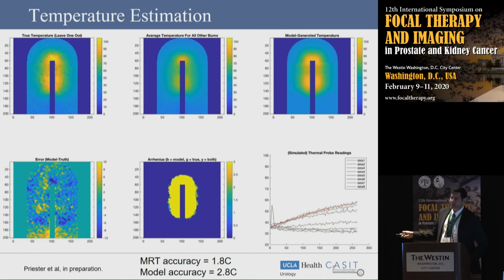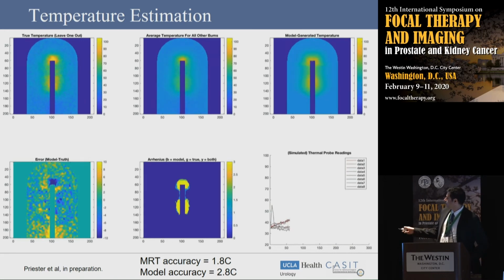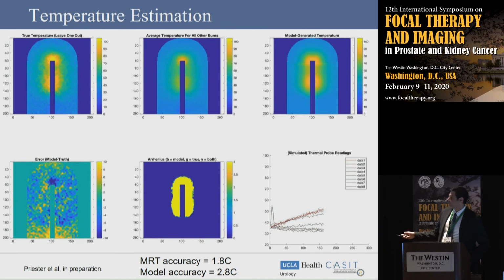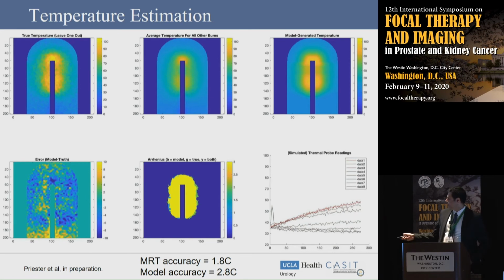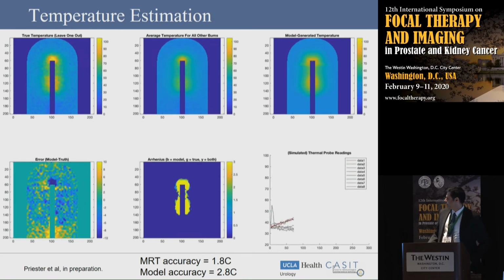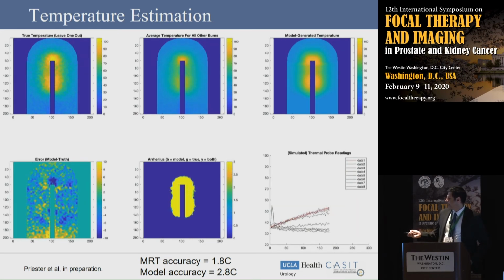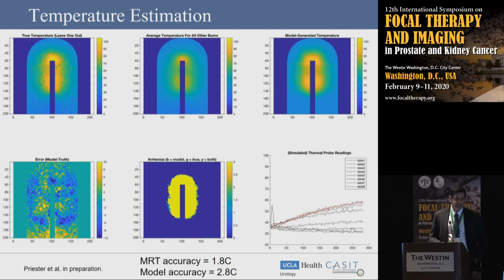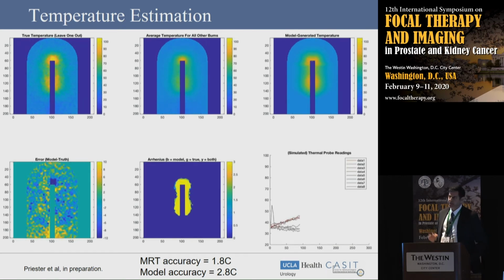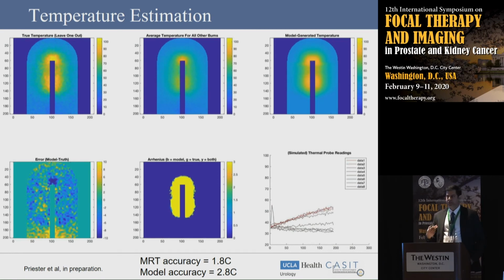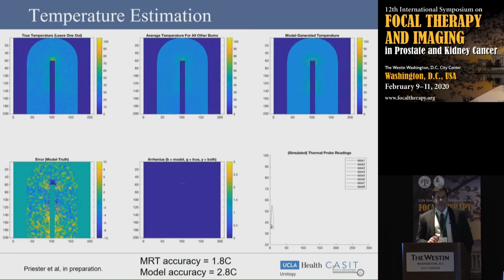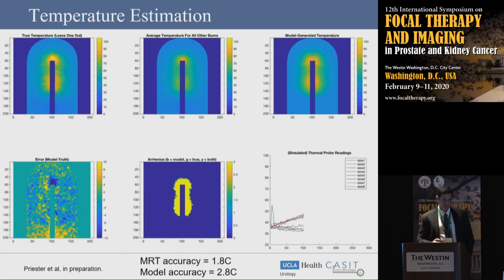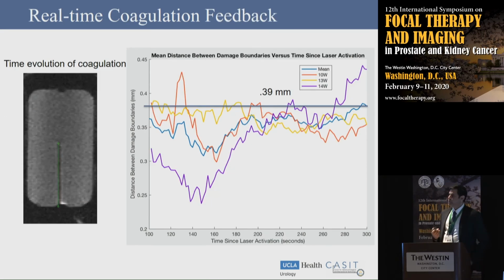You can see also the Arrhenius damage estimate, simulated thermal probe readings. This is comparing directly against MRI thermometry. And you can see our prediction closely matches the actual coagulation zone. We found that the MRI thermometry accuracy in an unmoving phantom was about 1.8 degrees. Our model accuracy approached that limit, about 2.8 degrees. However, we were basing this on simulated thermal probe readings, whereas our actual interstitial thermal probes have an accuracy of about 0.25 degrees C.